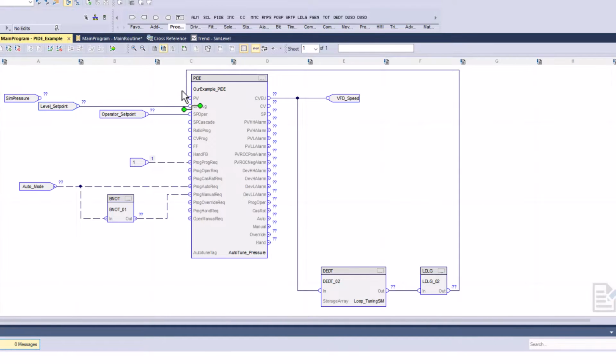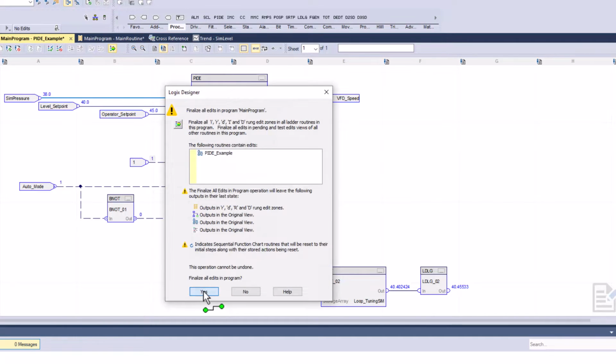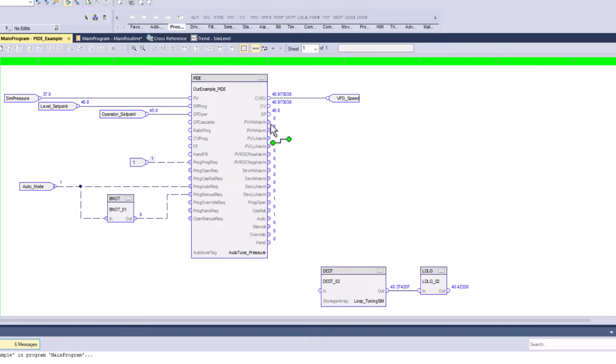We've effectively tested everything though, so let's take out the simulation logic and let's put the natural process loop in here. At this point, everything should work accordingly, and you should be very close. If anything, you need to manually tune, like just slight adjustments. But again, if you have your dead time and lead lag pretty close to the whole situation, like your whole loop, your external loop, your devices, your latencies and stuff like that, then you should be right in the ballpark. So just keep that in mind.